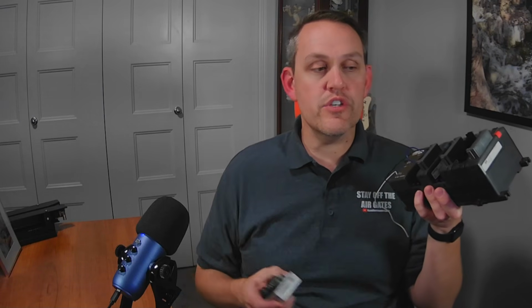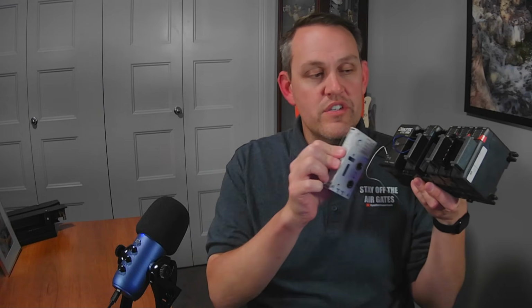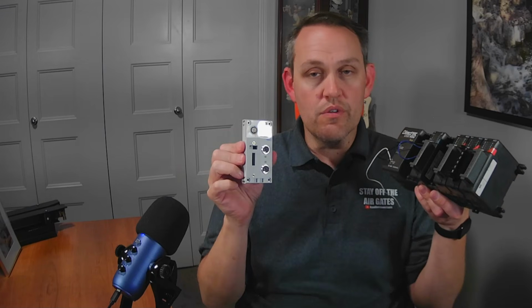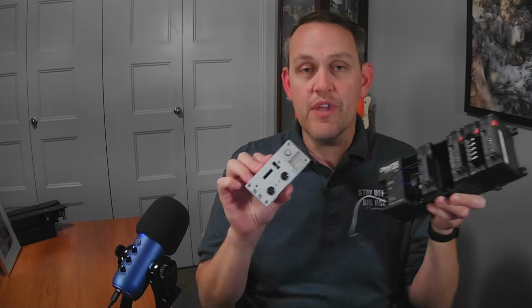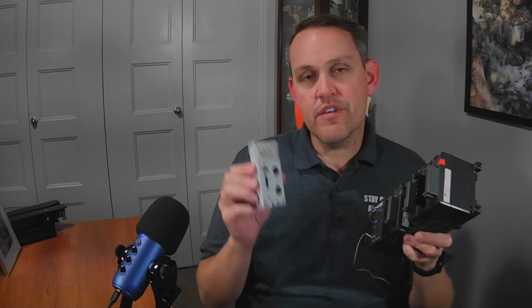So when we talk about other forms of safety circuits, the relays would do a similar thing. They would branch out the logic and send the same exact signals down two different sides of relays, both doing the exact same thing. And the relays had to agree with each other, otherwise the circuit didn't work. Not very executable in relays because you're doing the same logic commands, kind of hard to do. So what they came up with was safety PLCs. That is, here's my main PLC, and then I will have a safety. I'll use this as an example because it's a smaller version. My safety PLC watches the main PLC. It's got a digital watchdog on the inside, and the two watchdogs communicate with each other. The main PLC watches the safety PLC, and the safety PLC watches the main PLC.